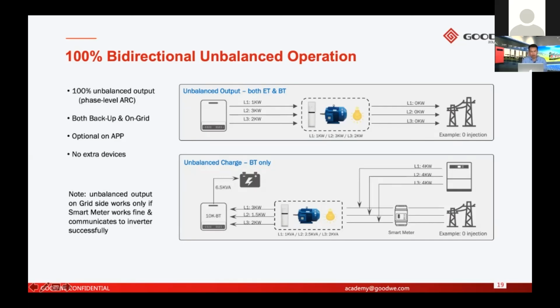So for these two solutions, we have some important features we should talk about here. The first is that it's 100% unbalanced output. And also, of course, the unbalanced charge is also 100% unbalanced. So what is 100% unbalanced? It means the max power charge or output on each phase is 33% of the nominal of the inverter. So for all three phases, the output or charge could be different, from 0 kilowatts to 3.3 kilowatts on 10 or 14 kilowatt inverters.